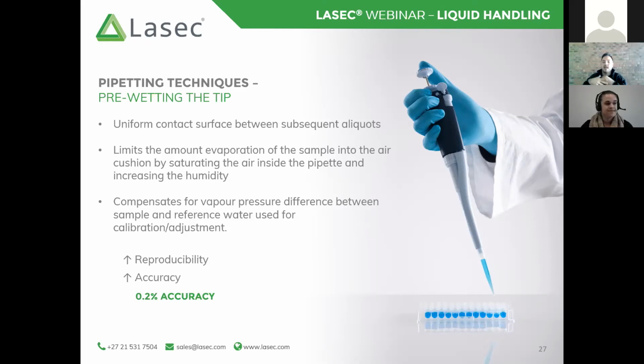So you are limiting the amount of evaporation, and the reason you are doing that is basically you are increasing the amount of humidity inside that tip. You are saturating that air pocket. It therefore cannot accept any more moisture, thereby protecting your sample. Your sample's not going to evaporate into that air pocket. You are going to be able to dispense exactly the amount that you had aspirated originally. Okay.